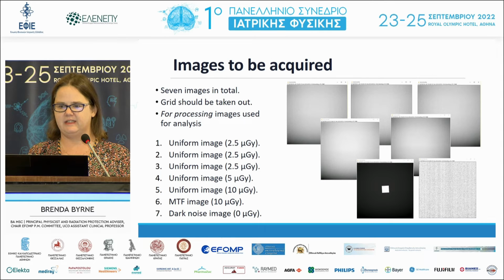So we have the 7 images. 4 or 5 of them are just uniform flat field images, and then we have one which we use for our tantalum target, which is for our MTF measurement, and one dark noise image.